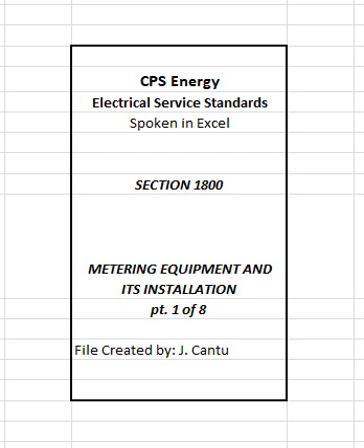C. No more than one conductor per phase or neutral shall be terminated within a meter socket with the exception of the Code 31 and Code 32 meter sockets. D. Conductors formed within the socket's enclosure must not be allowed to rest on or press against other terminals. E. Where metering equipment is connected using paralleled conductors, such conductors shall be installed in individual raceways and in the same manner on both line and load of equipment.